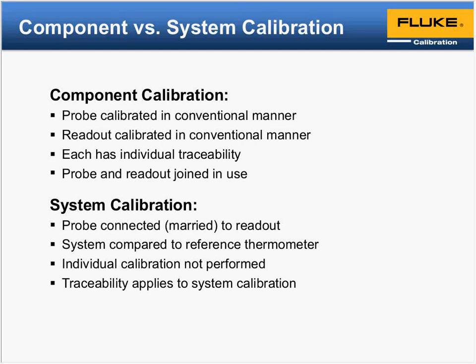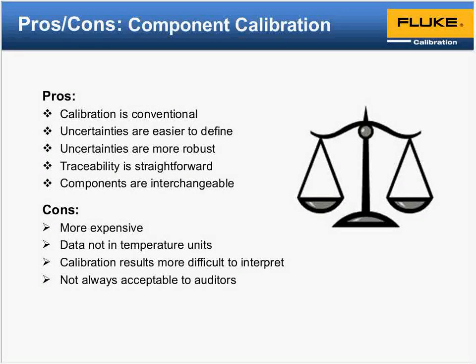Are there units for Drywells where you can accommodate more than, say, 3 to 4 UUTs, or if you calibrate thicker sensors? Depending on the Drywell and its capability, something you want to be aware of is the loading effect. If you have a well and you put a sensor in the hole, you may have some loading error to watch for. We also do custom inserts. I was actually working with someone who had a sensor that was 3/4 inch. The challenge there was matching him up to a Drywell that had enough capacity to immerse and control test that sensor without causing a loading effect on the Drywell. So again, yes, we do have options there.